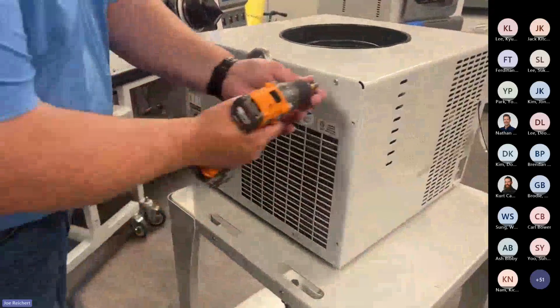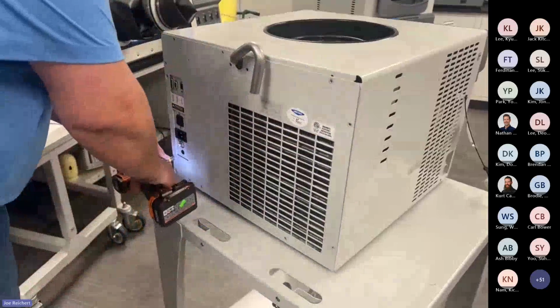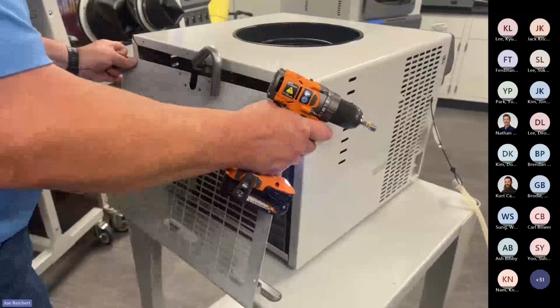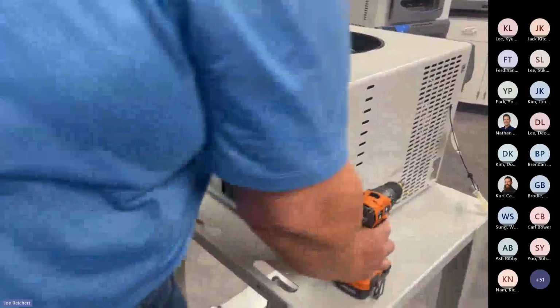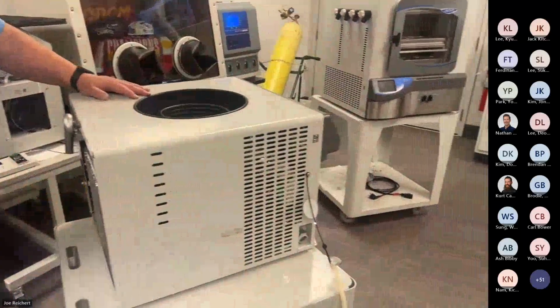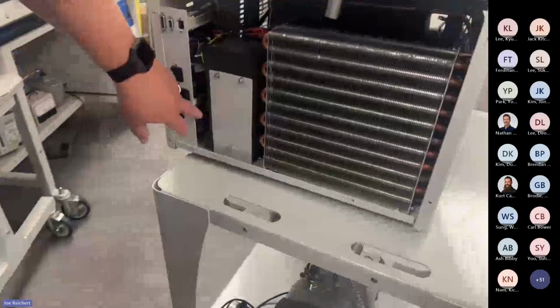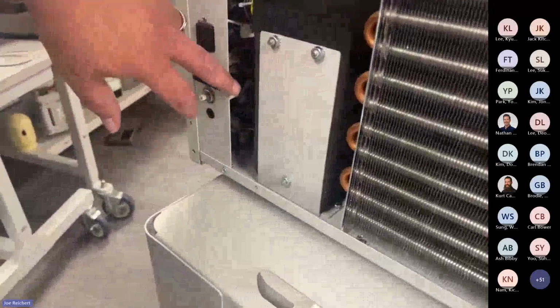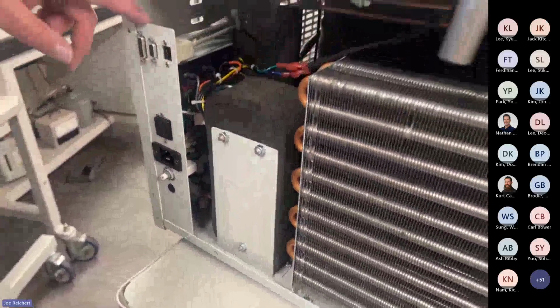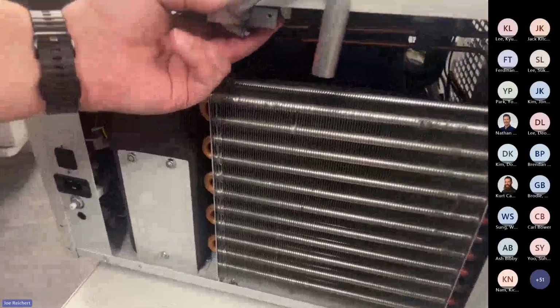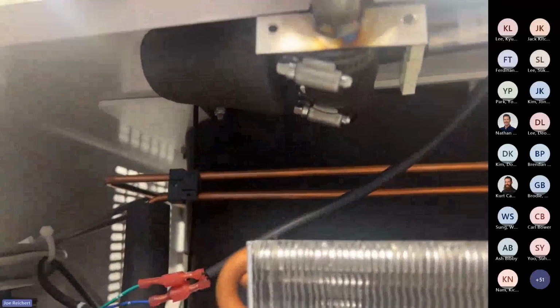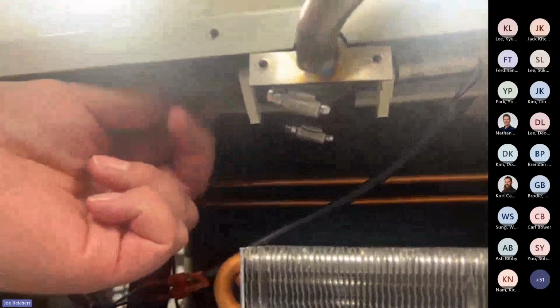Rear panel has a lot of screws in it usually, but we took a lot of those out. On the back side, this is where you'll see your condenser. You also see your power box has a few relays in it, has your power monitoring board, has your power supply board, and then you also have your heat exchanger on your -105 back here. Up on the inside is where we have that 4 rubber coupling that I was showing you that we use for vacuum leak test. It also has your vacuum sensor right here on this side, the little gray body. And then you also have your vacuum release valve on the other side. It's easy to see it because it has the white little filter on the end of it.